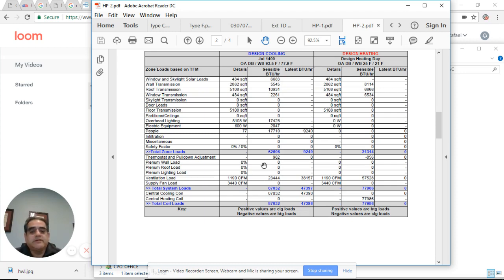Our biggest load, obviously, 23 plus 38. So that's like 40 plus 20, 60 and some change, right? 60,000 BTUs of outside air. That's 5 tons. 5 tons of outside air conditioning. Consider this: the size of the air conditioning unit just to control the ventilation load, the outside air load of 1190 CFM, is bigger than most air conditioners in people's houses for ventilation load.